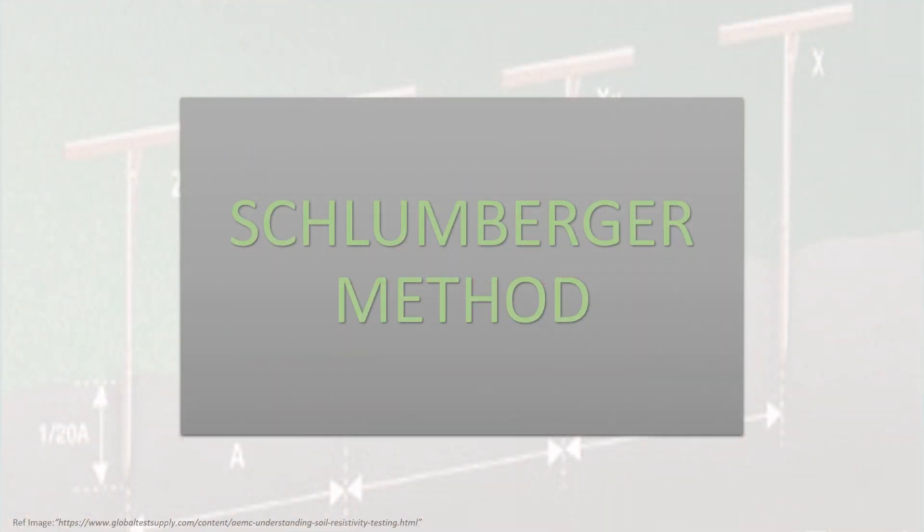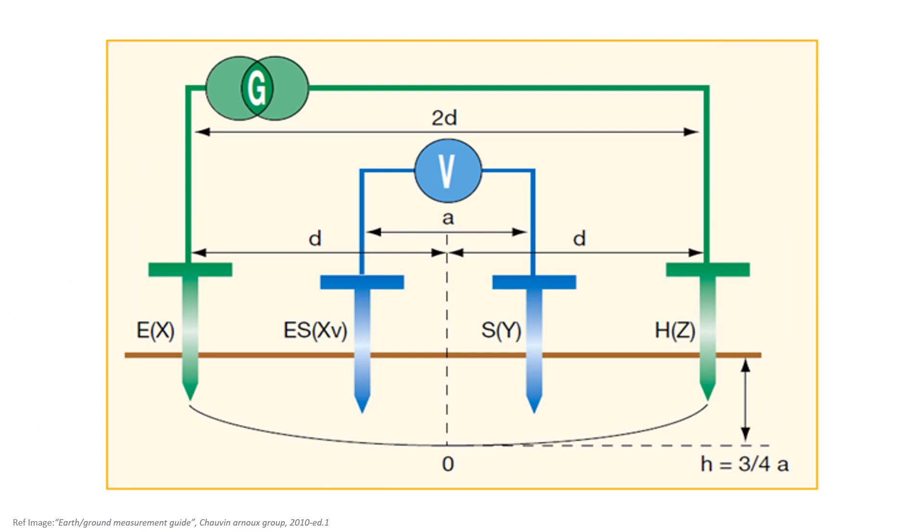The measurement principle of the Schlumberger method is based on the same measurement principle that the Wenner method. The only difference between them is the positioning of the electrodes. Now, the distance between the two outer electrodes is 2D, and the distance between the two inner electrodes is A.